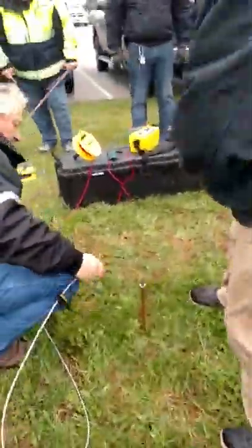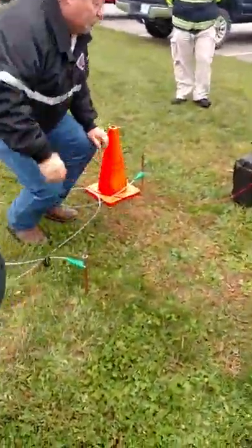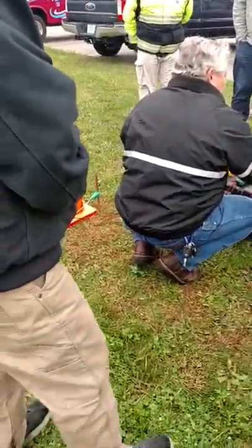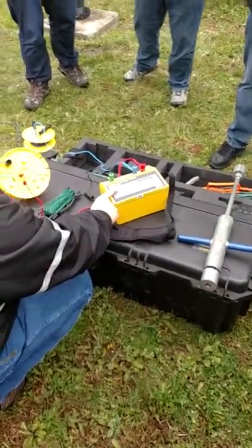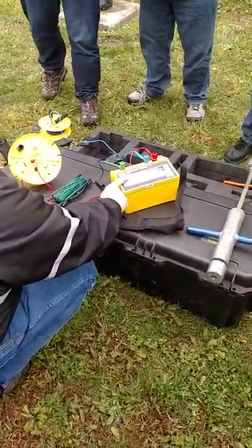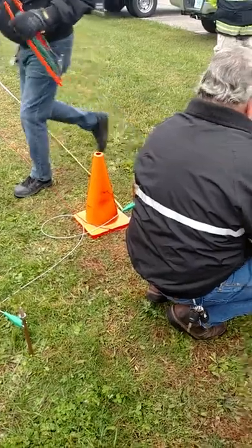So now we're going to bond these two rods together. We were at 44.2 last time. We're going to press and hold. We just doubled our surface contact area — we're down to 21 now. 21.1. So now being at 21, we're going to put another rod in.